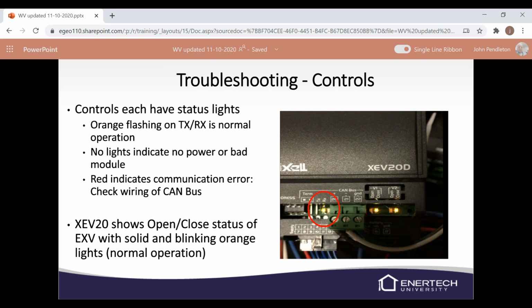Now I will get into a little bit of troubleshooting on the control because they each do have a light. This is the expansion valve board here basically, and it'll have an orange flashing as normal operation. No lights would be an indication of no power or a bad module, and a red light would indicate a communication error. A lot of times that's just the connection between the two has become loose. So you may need to pull that off and put it back on there. It will show an open close status with solid and blinking orange lights, which is normal operation.